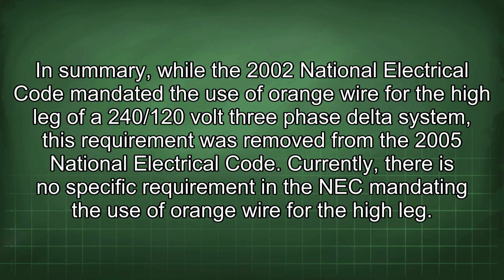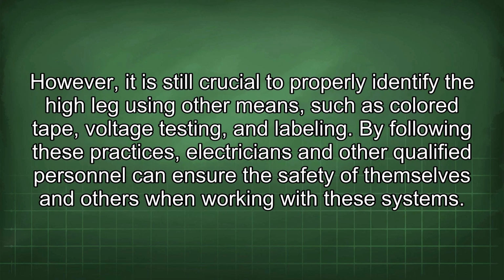In summary, while the 2002 National Electrical Code mandated the use of orange wire for the high leg of a 240/120 volt three-phase delta system, this requirement was removed from the 2005 National Electrical Code. Currently, there is no specific requirement in the NEC mandating the use of orange wire for the high leg. However, it is still crucial to properly identify the high leg using other means such as colored tape, voltage testing, and labeling.